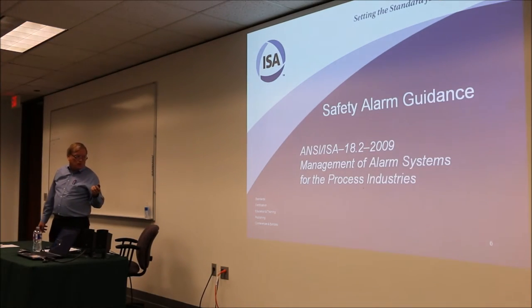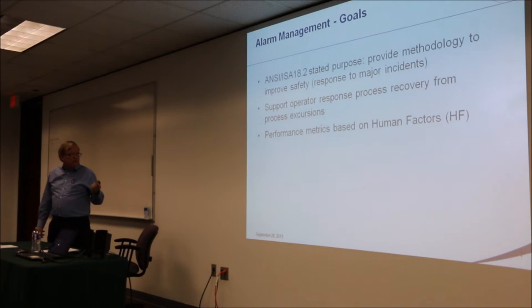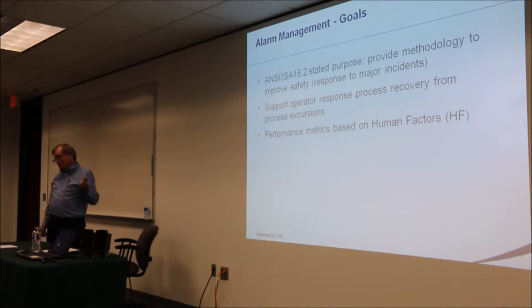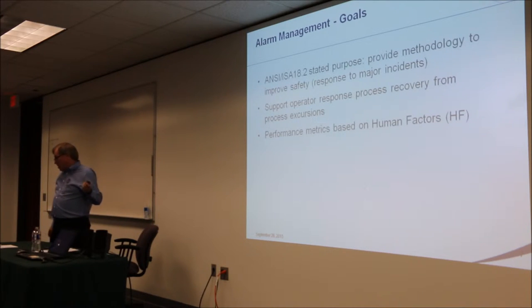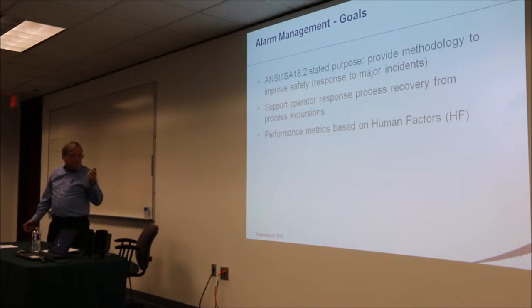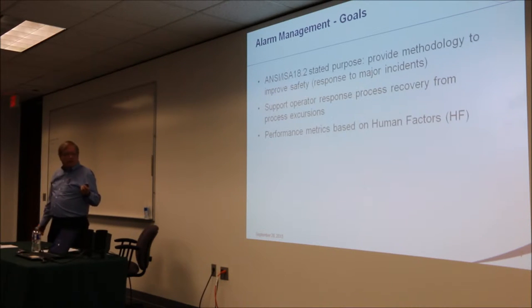We'll start with what's in 18.2 as far as safety alarms. Right at the beginning of the standard, the purpose is to provide a methodology to improve plant safety, and it was issued in response to some of the high-profile accidents that occurred as a result of alarms not being managed well. The other key point is that a successful alarm system is based on achieving human factors-based metrics, not a safety target the way ISA 84 would be.